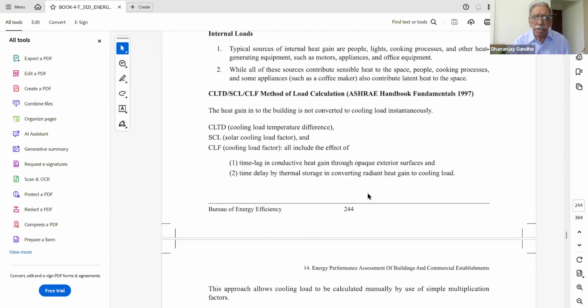They are basically, one is the CLTD, that is the cooling load temperature difference. The second parameter to be worked out is the SCL, that is the solar cooling load factor, and third is the CLF, or cooling load factor. So these three have to be worked out on the basis of the methodology given in the ASHRAE handbook. So those who are conversant with heat load calculation will know about it.